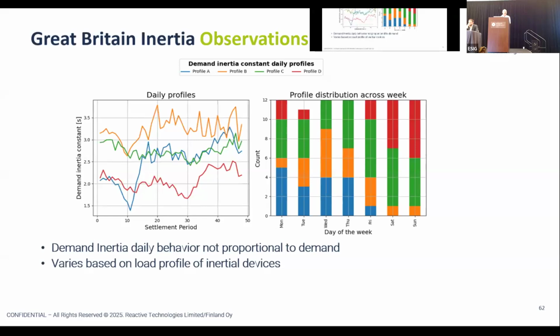If you go to the Australian power system, which has lots of mining activity, you see a completely different set of load profiles for the inertial load. In the UK, inertia from load typically makes up 20 to 30% of the system's inertia. In Australia, it can make up 40%, but a lot of it comes from mining, which is hundreds of kilometers away from the demand centers - presenting a different set of challenges around how you manage voltage, synchronous damping, and stability.